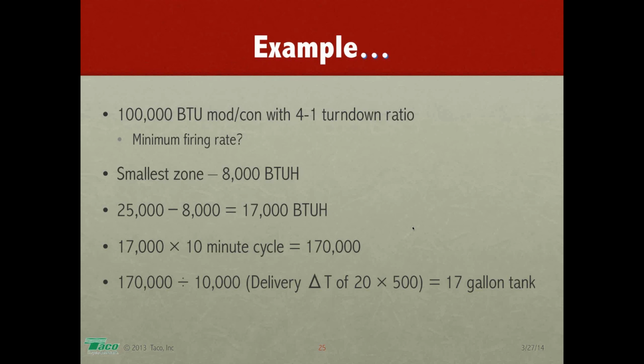Well, I can't find a 17-gallon tank. Okay, what can you find? I can find a 10-gallon tank. Okay, put in a 10-gallon tank. What would the net result be if you put in a 10-gallon tank instead of a 17-gallon tank? Well, your minimum burn cycle would probably be about 6 minutes instead of 10. It's better than 2, better than 30 seconds, better than 3 minutes. It's not as good as if it was a 17-gallon tank.